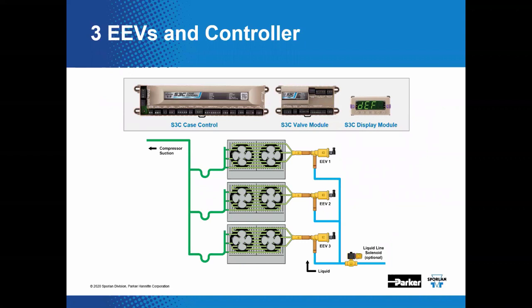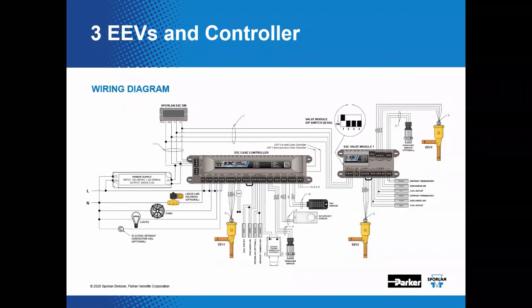Now, here's an example with 3 EEVs. Same kind of deal. You're going to need the valve module, because that extends the termination points and the ability to handle input and output that limits the S3C case control. Right. And here we've depicted, again, it looks like there's an undue amount of detail here, but really it's quite simple, this wiring diagram. We've got the S3C case control. We have the valve module, which extends its capabilities. And you can see here that we have 3 EEVs terminated, pressure transducer, and the solenoid valve. And then, of course, over here is the display module.